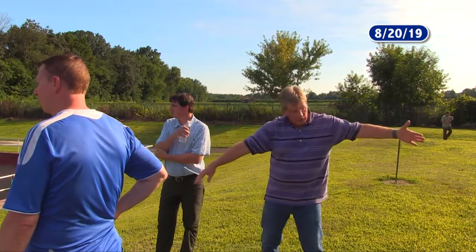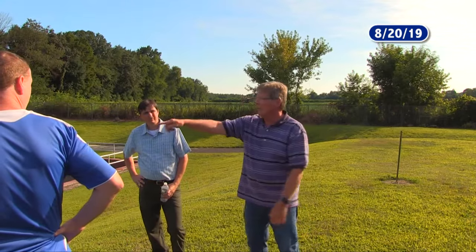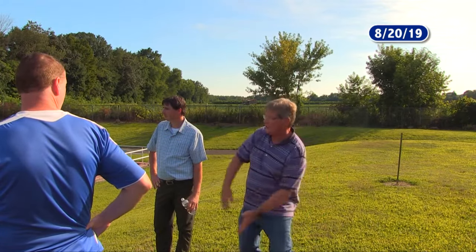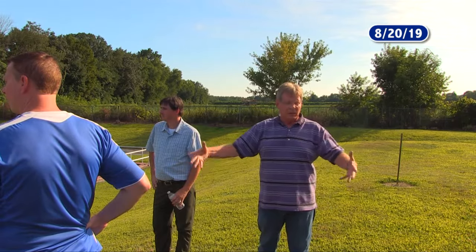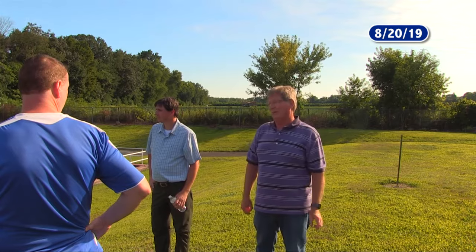So the flow's coming in, the grinder grinds up trash and makes it smaller trash, and then it goes through, and then the return sludge or microbes come in right there through that pipe, and then all of them swirl around and go down a hole and come out in the middle of the tank. And then the aerator is cycled on and off an hour at a time, 100% on, 100% off. Full nitrification, full denitrification, all in one tank, and it's working out really nicely.